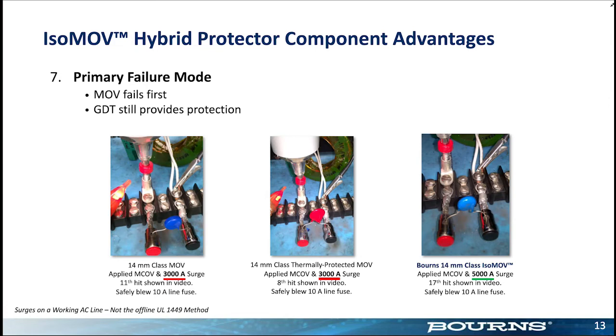this is to put the device in line, right, with 120 hertz, 120 volts, AC, make sure it works, take it offline, surges, goes through that surge process, puts it back online to see if it passes, and sure enough, it would pass. This test that we're doing is a more realistic test. We surge it while it's active on that AC line at the same time, which is not what UL does. And for this particular case, you'll see that the thermal fuse did not activate.